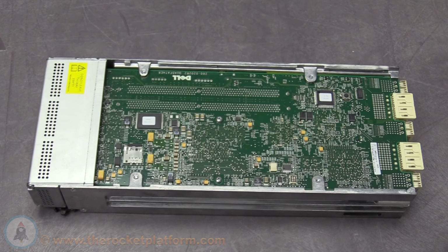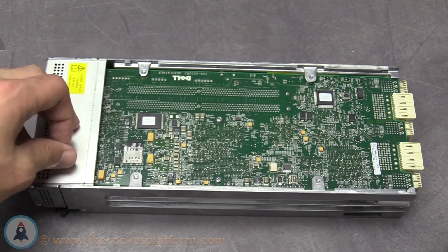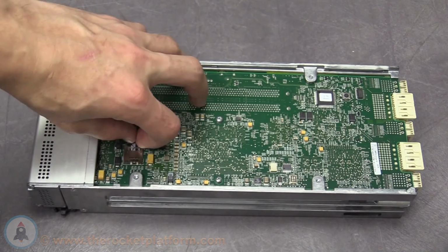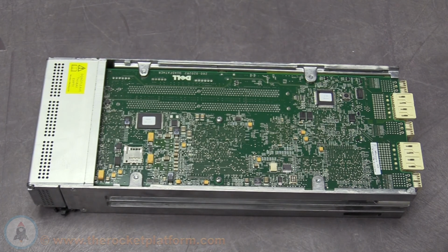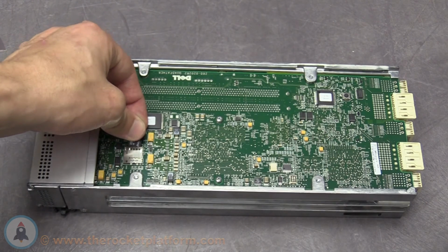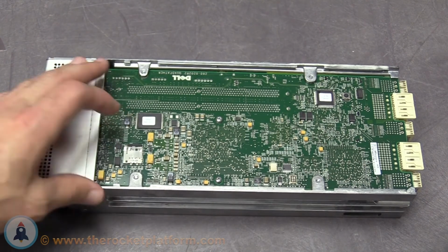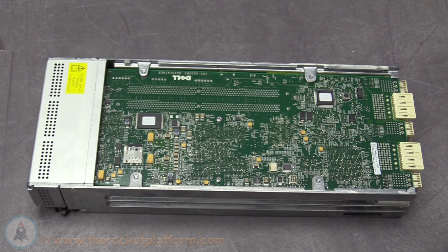You must now move the SD card from the faulty controller to the replacement controller. On the bottom of the faulty controller, you will see the SD card in the SD card slot. Push in on the SD card, releasing the locking mechanism. Pull the SD card out of the slot. Now insert the SD card into the SD card slot on the replacement controller. Push in until you hear or see the SD card click into place. Once clicked in place, the controller will be safe to insert into the machine.